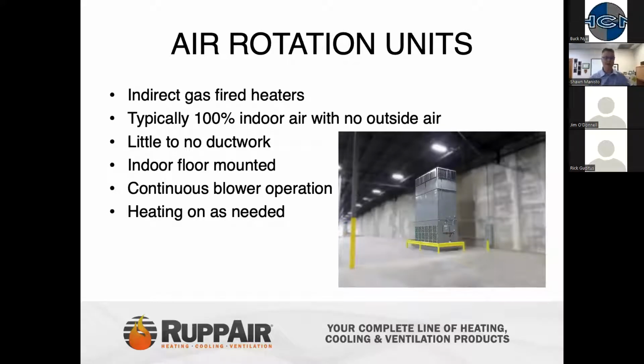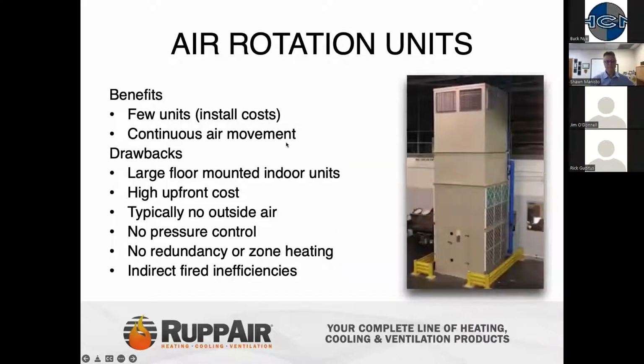Next, we get into the air rotation type system. The air rotation type system is another indirect fired heat source. Typically, these are 100% inside air or recirculating air. This image over here just shows you what they would look like, basically having 100% return air coming into the system, getting heated up, and then getting discharged across the building. Some do have the ability to bring in some level of fresh air, but typically they are not. Indoor floor mounted, continuous blower operation, and heating to meet heating needs. The biggest benefit on air rotation systems is very few units, but continuous air movement. The biggest thing is that this is a dated product now from the standpoint of having HVLS fans available. We're going to talk more about those later.